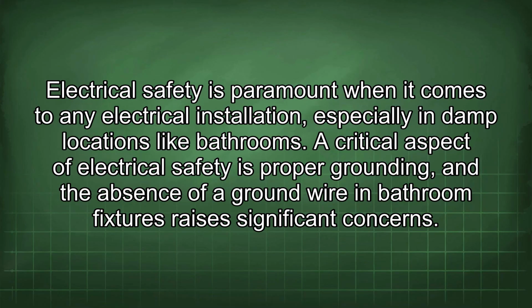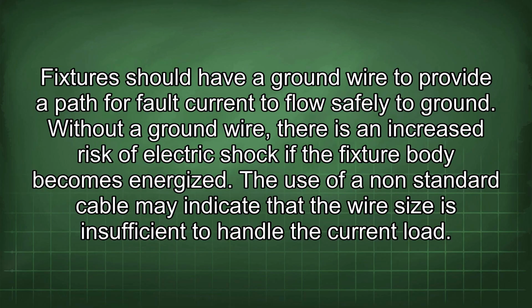Electrical safety is paramount when it comes to any electrical installation, especially in damp locations like bathrooms. A critical aspect of electrical safety is proper grounding, and the absence of a ground wire in bathroom fixtures raises significant concerns. Fixtures should have a ground wire to provide a path for fault current to flow safely to ground. Without a ground wire, there is an increased risk of electric shock if the fixture body becomes energized.